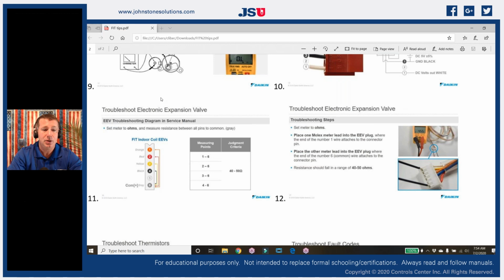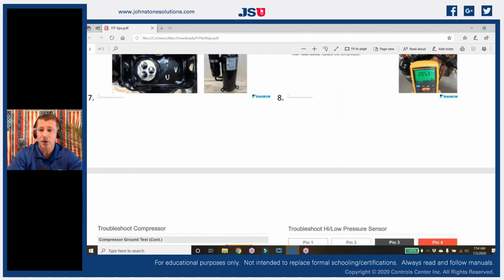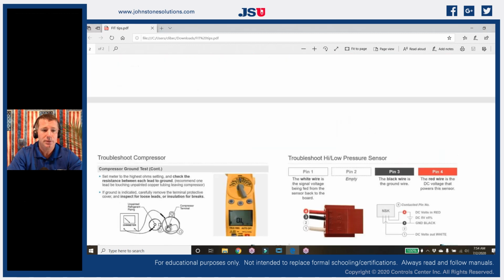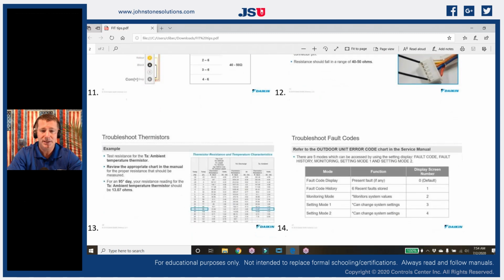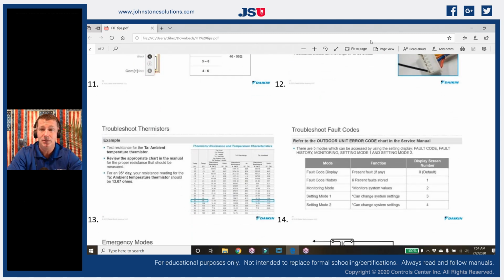Now, if I go into our thermistors, we were talking about the thermistors being the same thing. It's just a change in resistance, right? That's all temperature thermistors do, is they change resistance when they change temperature. So we can do the same thing. We can see what voltage is coming through our thermistors, because we're going to use that 5-volt DC again. Our generator's producing it. Why not use it for all of our controls?